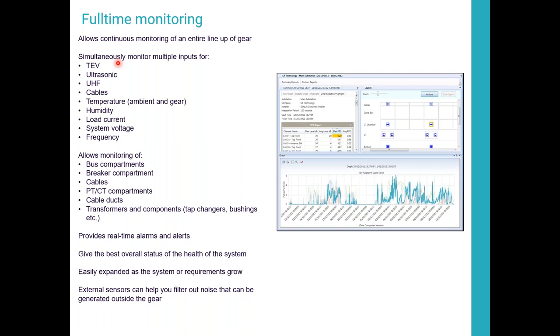One of the paper mills I did, I could hear the PD from the outside. I went down and measured every cubicle. And when I put it on a plot in a chart, I was actually able to see the amplitudes increasing on each section until I got to the one that was making the buzz coming out of it, and they dropped as I went down.